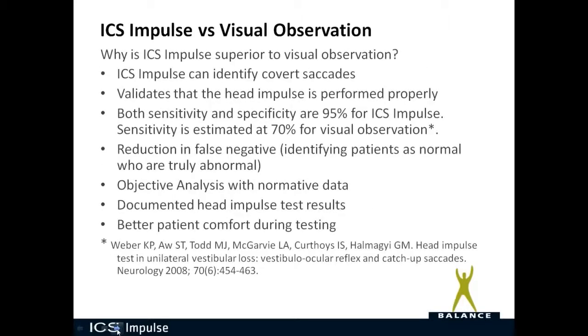Let's talk about ICS Impulse versus visual observation. ICS Impulse can identify covert catch-up saccades, and it validates that the head impulse is performed properly. Both sensitivity and specificity are 95% for ICS Impulse, while sensitivity is estimated at only 70% for visual observation. This reduces false negatives — you don't want to miss covert catch-up saccades and identify abnormal patients as normal. With ICS Impulse, you identify both overt and covert catch-up saccades and don't misidentify anybody.